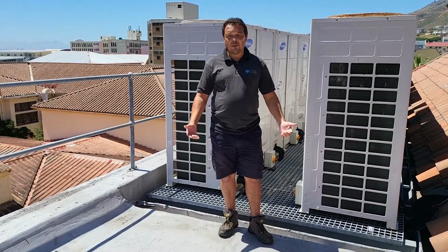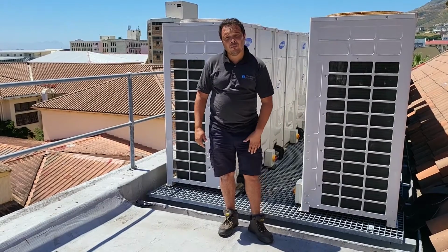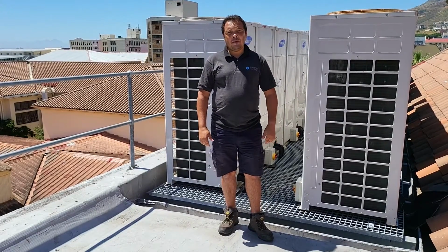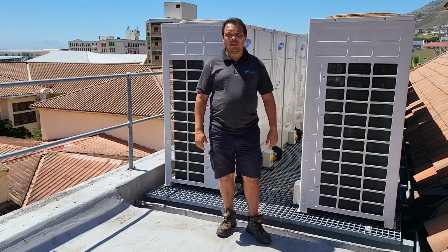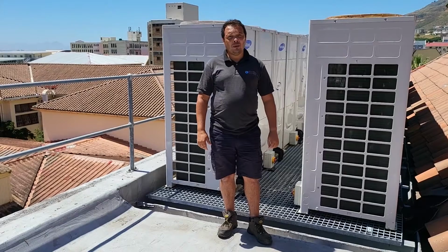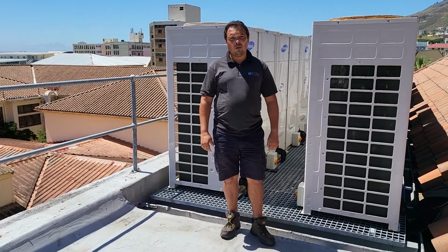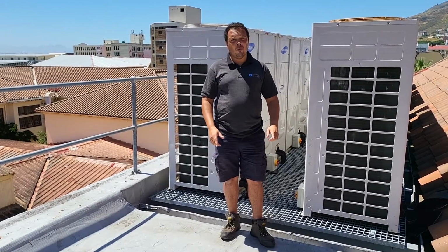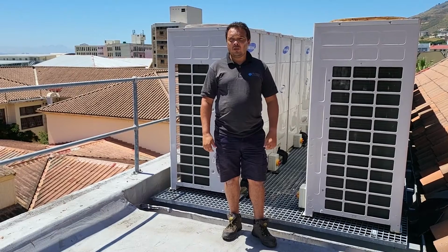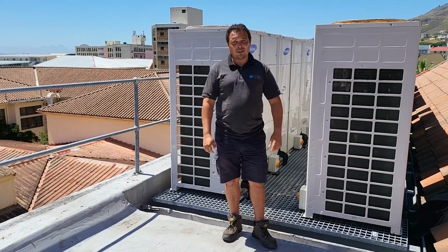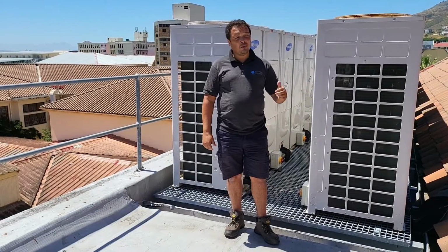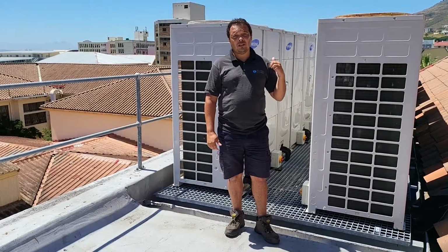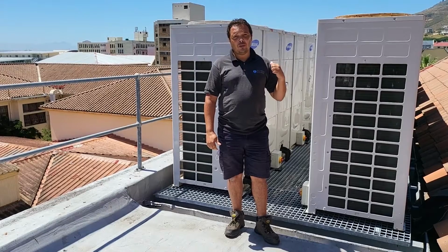That's something simple enough that we can pick up from the SNET software. And the other error code, the 215, is consistent with duplicate addressing between one or more MCUs. So the first thing we're going to do is connect our SNET software so we can take a look at what's happening, and then we also have to physically go into the roof space and check what the addressing is on the MCUs.